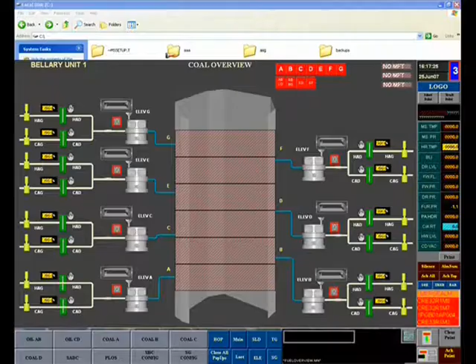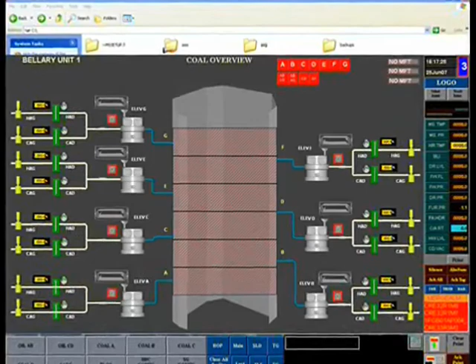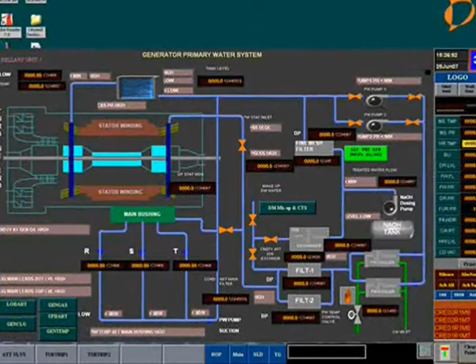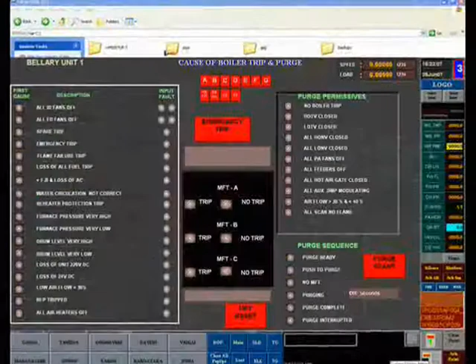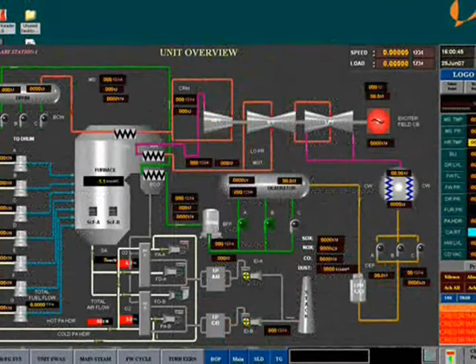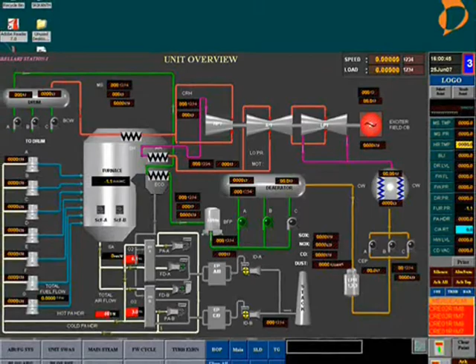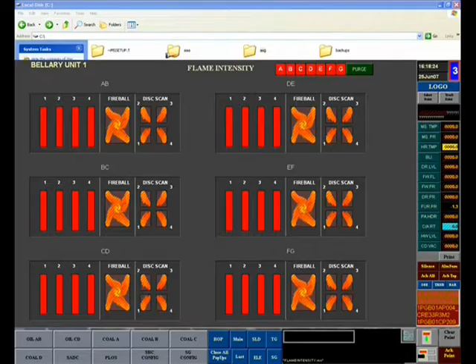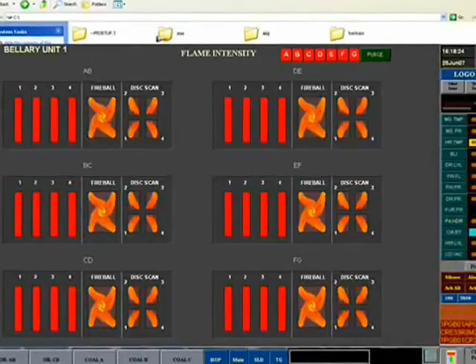Instrumentation engineers rushed to the spot and found the parameters relating to the generator auxiliary system and furnace safeguard supervisory system seriously affected. Some of the process control, protection and interlock systems of the equipment were also affected. The total power plant automation control system was switched off. The systems related to the barring gear, generator auxiliaries, and air preheaters were retained. Operation personnel had to rush to the local spots to ensure the status of the emergency systems. Some of the control panels were already affected by the secondary effects of the fire.